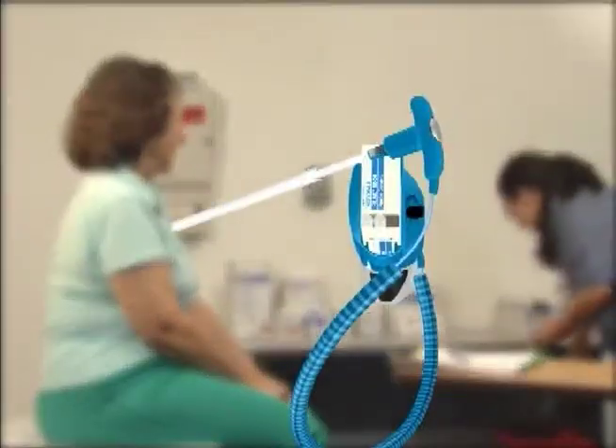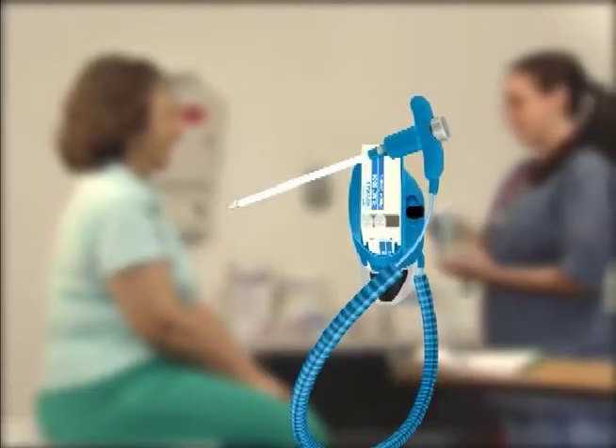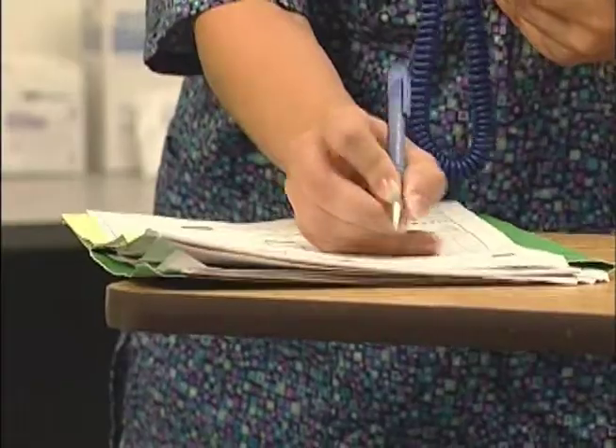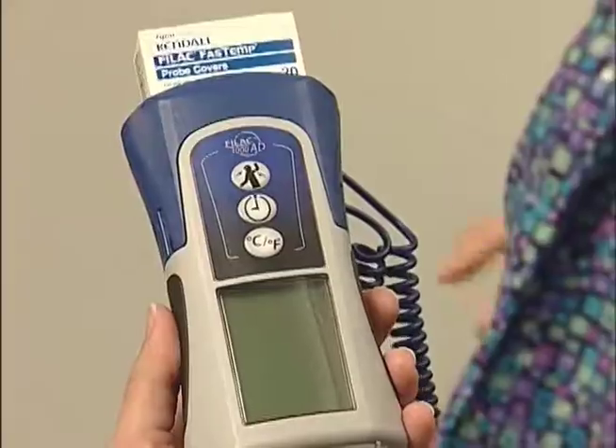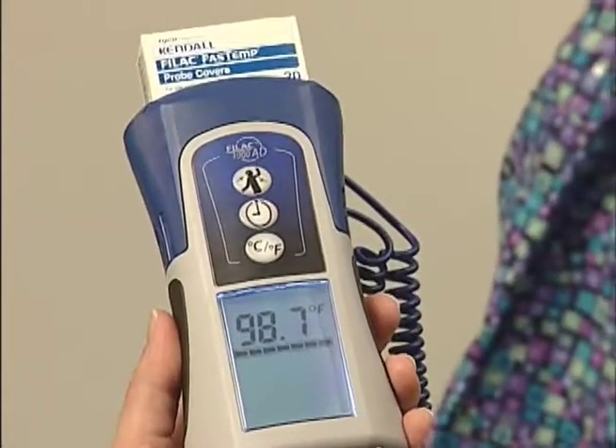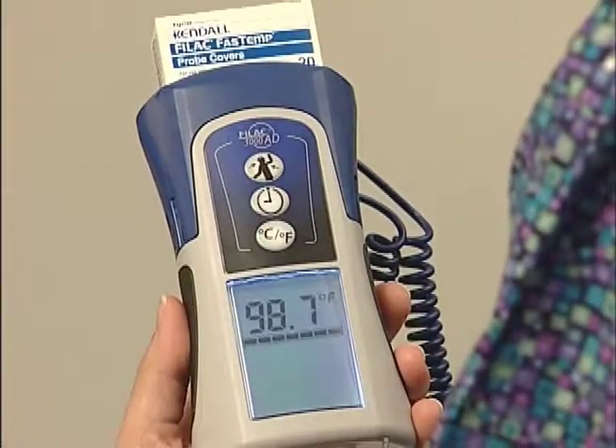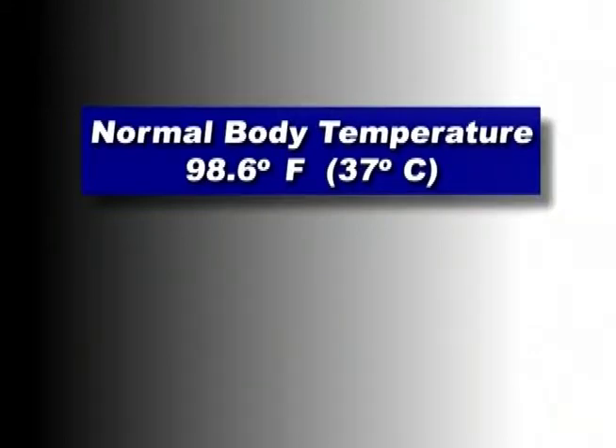When you have completed the temperature reading, discard the probe cover into a medical waste container by pushing the button on top of the probe and return the probe to the chamber. Document the reading in accordance with your facility protocol. The last temperature measurement is stored for recall until the probe is once again withdrawn from the isolation chamber. The amount of time required to complete a temperature measurement depends upon the site and operation mode selected. It is a common myth that 98.6 degrees Fahrenheit, 37 degrees Celsius, is everyone's normal body temperature.